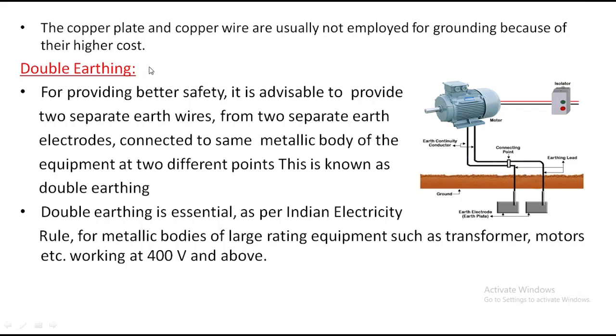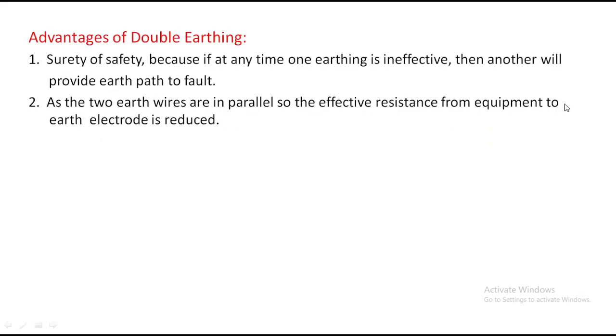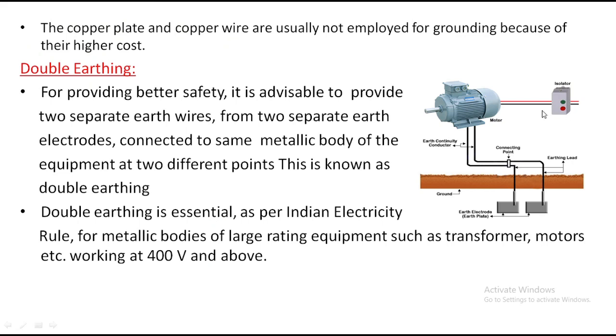The next earthing is double earthing. As the name itself says, we have to put two wires for earthing. Look here, this is the motor. The power supply comes to the motor, and we put one earthing wire and we use another earthing wire. These are connected to one plate and another plate. If there is any leakage, the leakage current will flow from this to the earth electrode and into the ground. Here also it is useful.